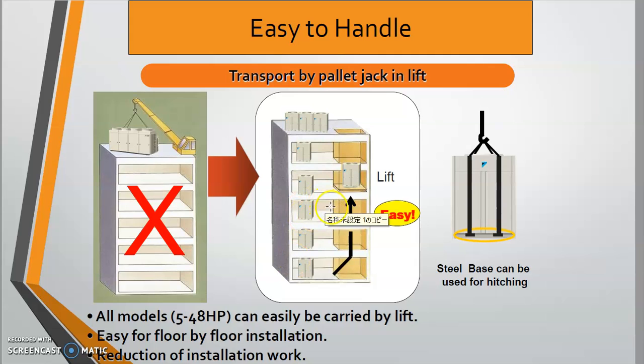But compared to the VRV system, we can easily use a pallet jack, and we can use the lift to uplift our outdoor unit to be put maybe on the rooftop or in any location that we want. So usually all models of outdoor unit for VRV system from 5 to 48 horsepower can easily be brought and fit into the lift. So it is also easy for floor by floor installation, or up to the designer or our engineer where we want to put the outdoor unit. So of course this will reduce a lot of installation work.